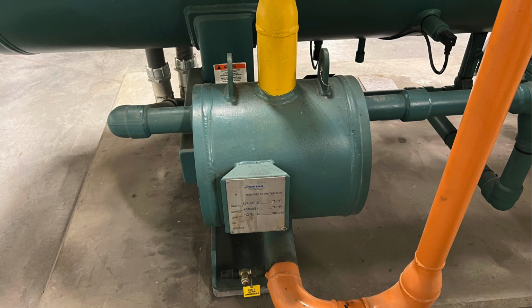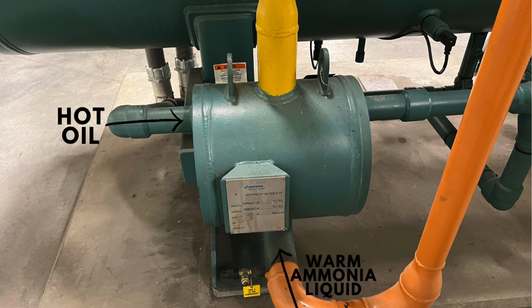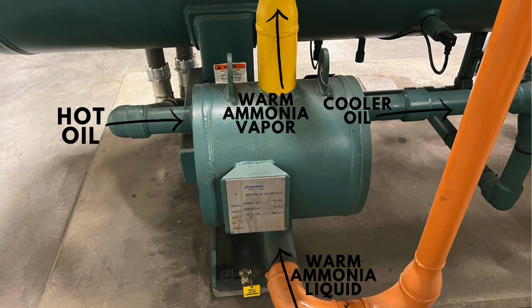The heat exchanger has two circuits. The first circuit receives hot lubricating oil from the screw compressor. The oil is cooled by the warm ammonia supplied from the thermosyphon vessel. As the oil transfers heat into the liquid ammonia, vapor is formed, which is returned to the thermosyphon vessel. Reduced temperature oil exits the heat exchanger and is returned to the screw compressor.